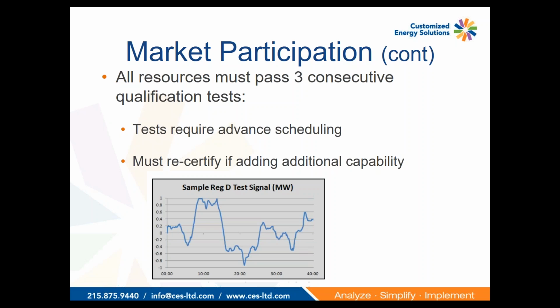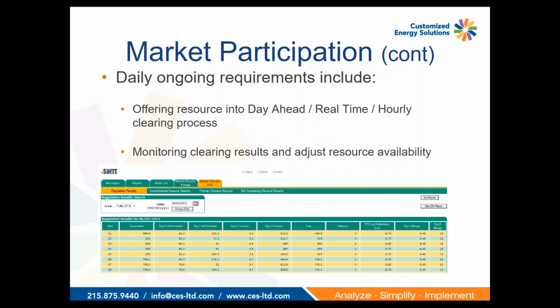And then just as an example on the slide there is the actual regulation test signal that PJM issues for storage facilities. It is a signal that's posted out on the web, so you can download it and actually use that as a sample or as a test signal for yourselves to make sure facilities are able to follow.